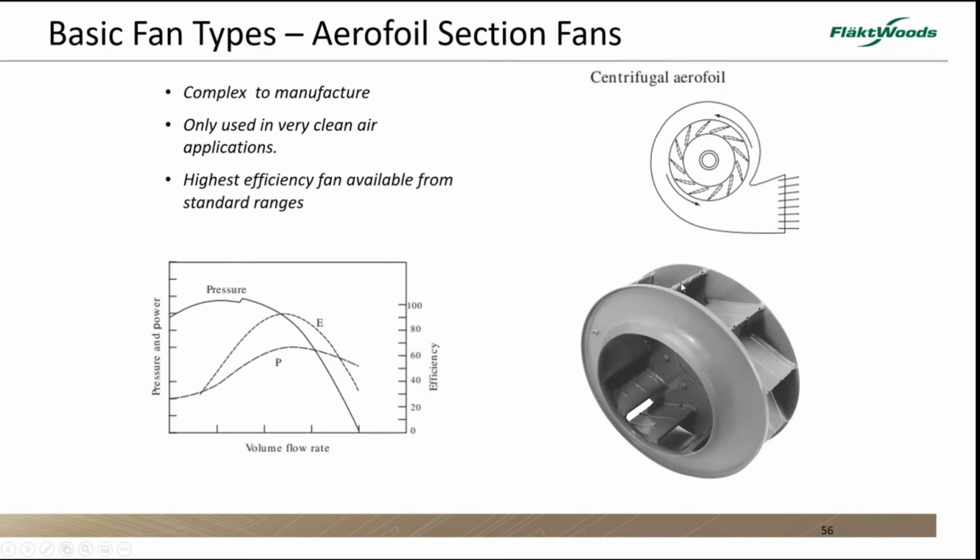But you can see that if you're going to have an aerofoil section, you've got to fabricate that. If you fabricate it and you have the welded construction, you must allow the gases to get out. So while the efficiencies can be phenomenally good, it's complex to manufacture, and you can only use it in clean air applications. So you'd only see it in very high specification applications.